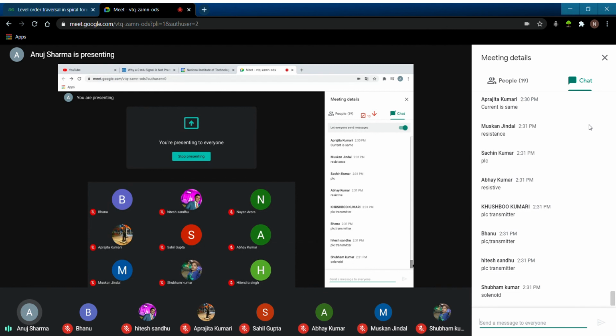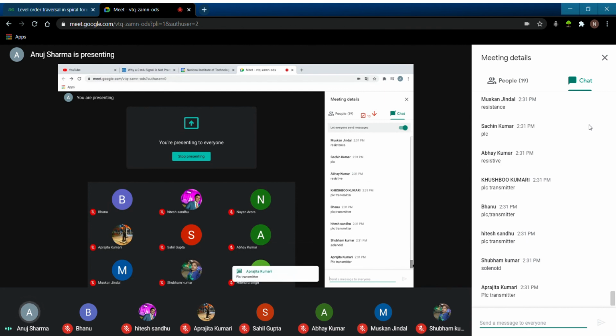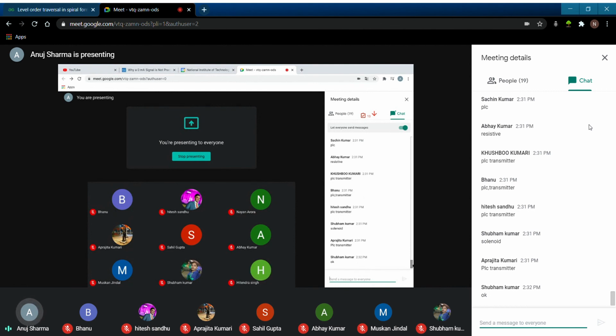But actually, if we are talking about a sensor - the sensor is going to give you a sense, and it might be converting it into a voltage signal through a transmitter only. So there will be a PLC transmitter, and then it will give it to a controller, and in the controller there might be a recorder which records or collects it. So these kinds of loads can work, because we are talking about a 4 to 20 milliamp for a particular sensor. So your total voltage can be distributed amongst transmitter, it can be distributed among PLC, but current is same throughout the loop. That is why you use 4 to 20 milliamp.